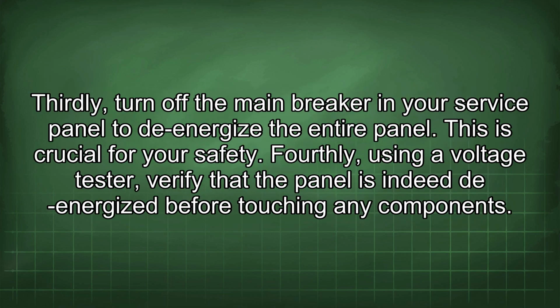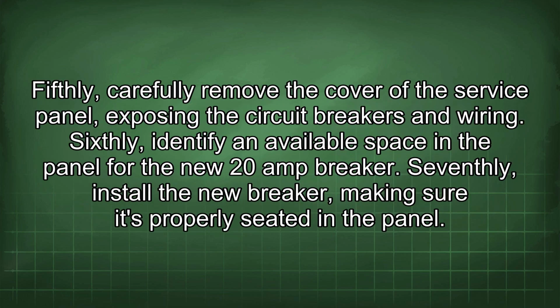Thirdly, turn off the main breaker in your service panel to de-energize the entire panel. This is crucial for your safety. Fourthly, using a voltage tester, verify that the panel is indeed de-energized before touching any components. Fifthly, carefully remove the cover of the service panel, exposing the circuit breakers and wiring. Sixthly, identify an available space in the panel for the new 20 amp breaker. Seventhly, install the new breaker, making sure it's properly seated in the panel.